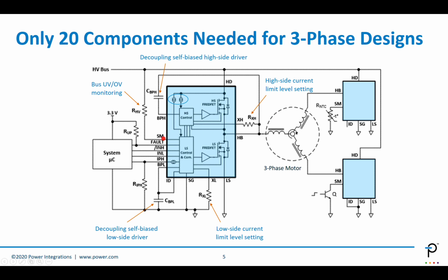There is also a pin here called the system monitor pin, which can be used in 3 different configurations. One is monitoring the high voltage bus through this resistor, and it can provide different trigger levels for UV and OV protection. Another way of using the SM pin is to monitor an external NTC. It's also trigger based: when, for example, 150 degrees Celsius is reached, the BridgeSwitch notifies the microcontroller through the fault bus. You need to imagine all of these 3 BridgeSwitches, each one having, of course, the fault bus pin. All of the fault pins are connected to each other, and through a pull-up to a 3 or 5 volt rail. It's similar to an I2C bus.